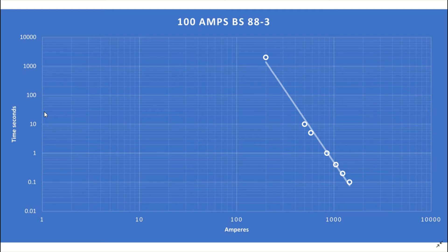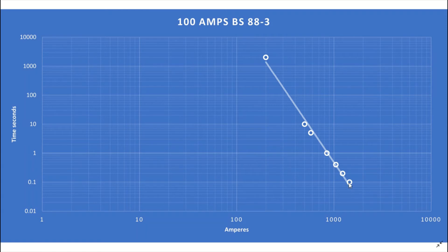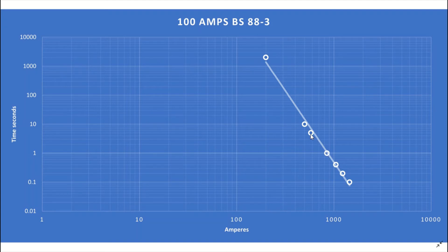In the charts in the regs book you'll notice that there is a table on the top right hand corner of the page. The table provides the minimum current required to operate the protective device within the disconnection times and I have used the same values to plot the curve on this chart. So here we have the values for 0.1, 0.2, 0.4, 1 and 5 seconds.